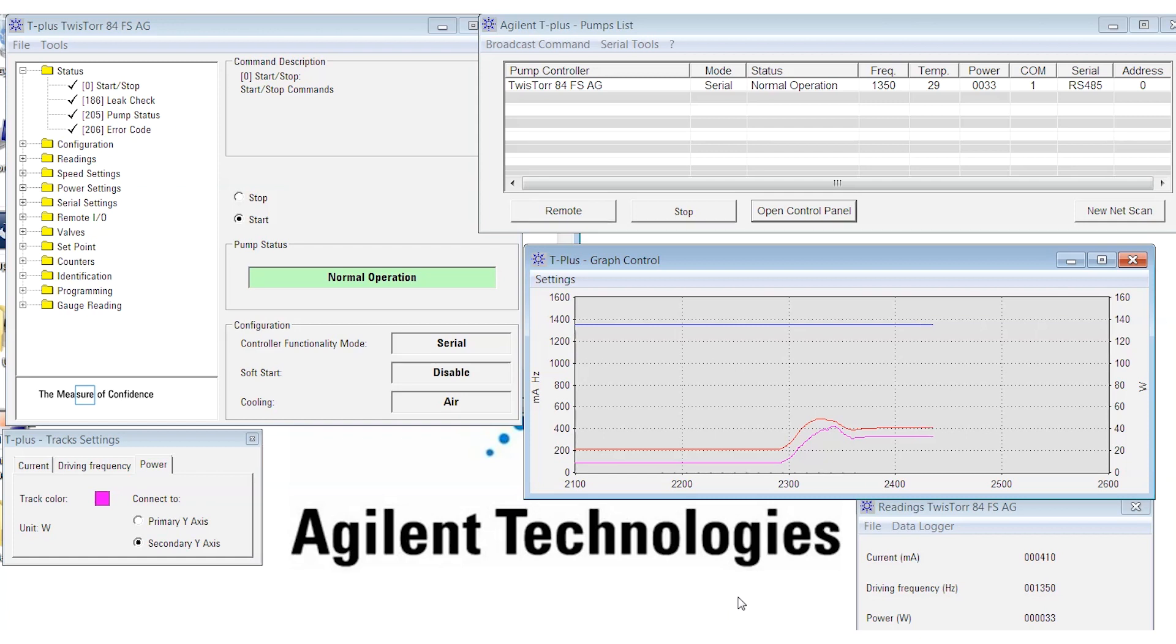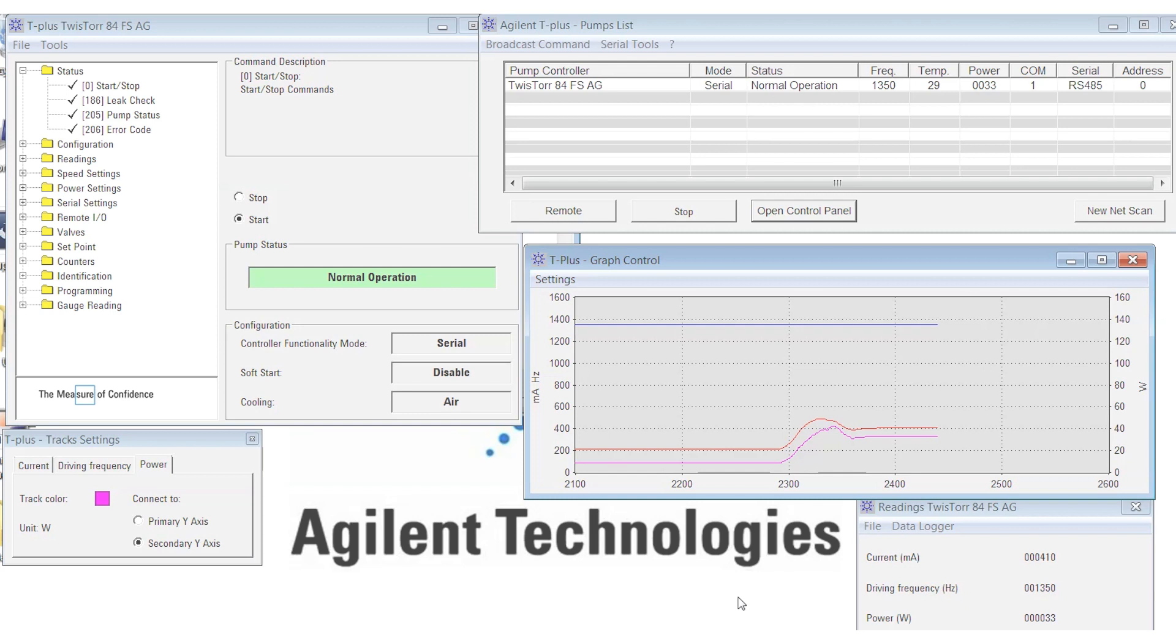With this gas load, I would recommend adding a cooling fan to the system just to get that temperature down a bit. The 84FS has an upper temperature limit of 65 degrees C. Above that, the controller will shut the pump down. But we want to stay well below that for optimum reliability.